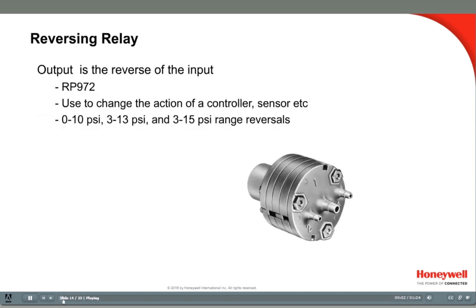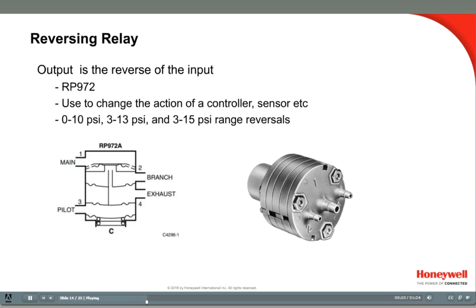A reversing relay does just that — it reverses a pneumatic air signal. This relay might be used to reverse a branch line signal when the actuator's action is out of sync with the rest of the control logic. Or it can be used to reverse any pneumatic pressure signal, such as sensors, controllers, or another relay's output. Port 1 is for main supply air, and port 3 is the pilot signal from the branch line that needs to be reversed. Port 2 is the output with the reversed signal, and port 4 is the exhaust.